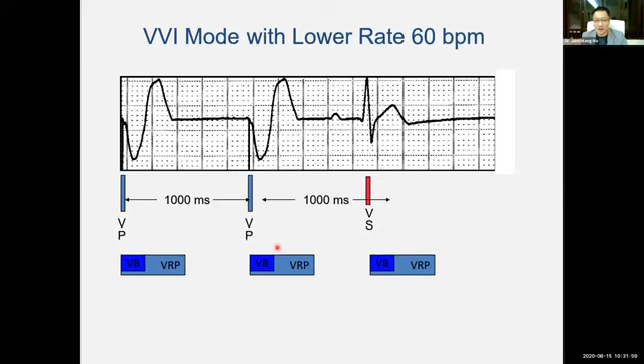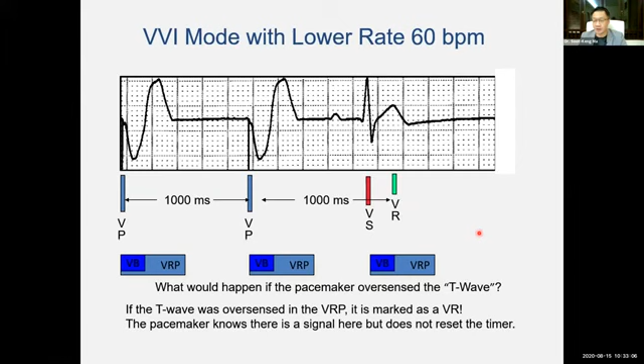Now, I want you all to look at this. The T wave is falling into the ventricular refractory period. Now, at that moment, the pacemaker will still be able to see the T wave, as in a cardiac electrical activity. Now, remember that a pacemaker will not be able to tell which is a QRS complex, which is a T wave, because it can only see electrical activity, as in a spike. So, what if it mistakes this as another ventricular event, as in a QRS complex? Without the refractory period, if we initiate, set the timing cycle again, saying, oh, there's a QRS complex here, so inhibit myself, V, and I inhibit myself. So the patient will be left with a long pause, if not for the refractory period here, which is crucially important.